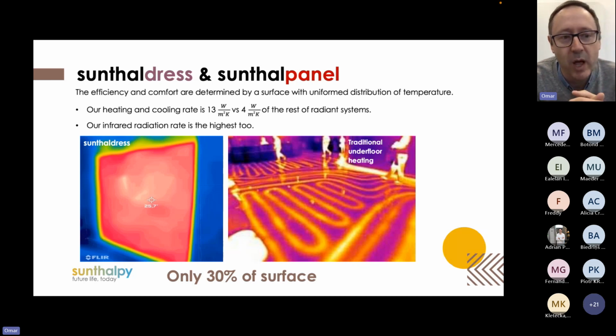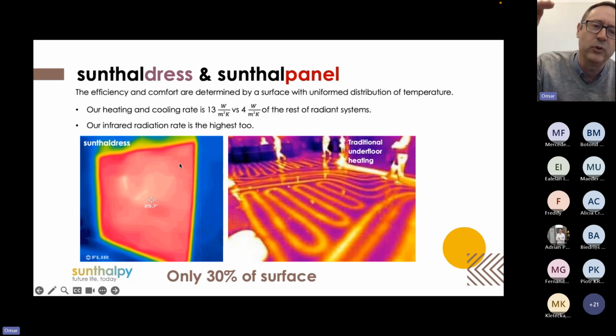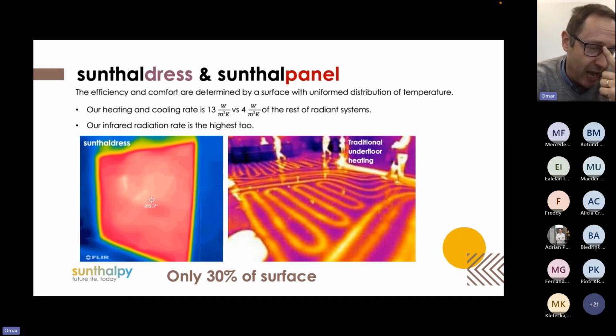On the left, we have one of our systems, our plates. You can see we have a uniform temperature, you cannot see where the tubing is, because the materials we deploy are very high conductivity, giving perfect diffusion. Our circuits work with a temperature differential between input and output of 2-3 Celsius, and the average temperature of our plate is always between both, so we're making a perfect thermal transfer.